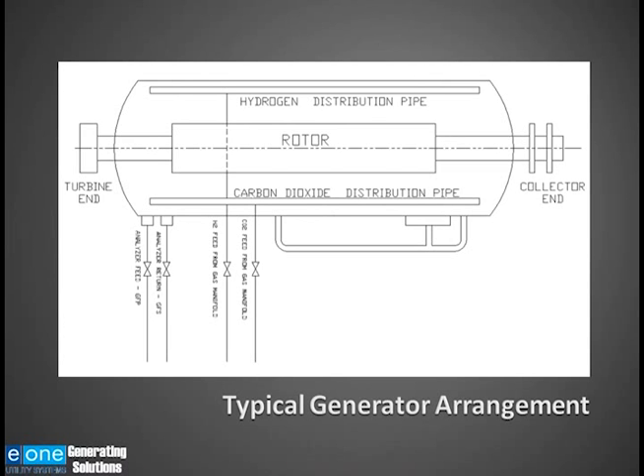The carbon dioxide is fed through the bottom header of the generator. Because carbon dioxide is a heavier gas, it will force the hydrogen or air out the top header. So the hydrogen and air will come in through the top header. And then over to the left-hand side, there are 2 points where the analyzer takes its sample. Now that's during normal operation. And it's very important to note that you take a sample of hydrogen during normal operation across the fan of the generator. But during the purging process, you're going to be taking your sample at the vent line, which I'm going to show in a couple slides.